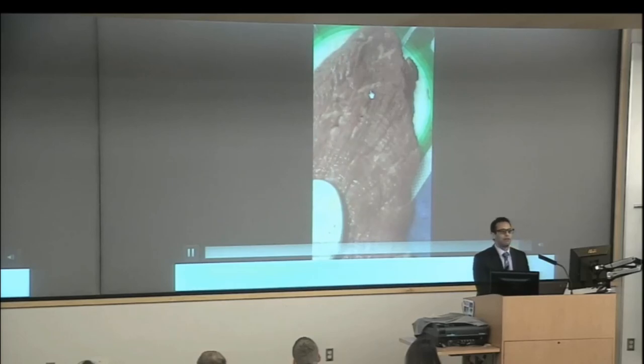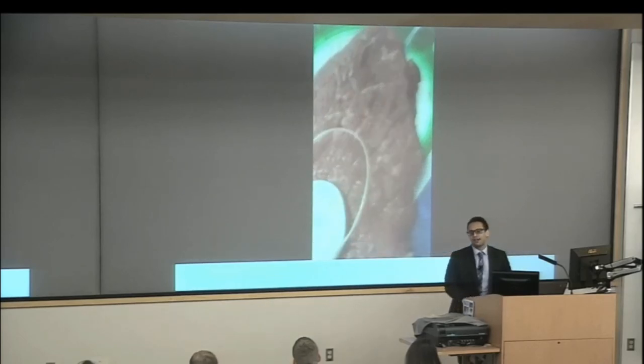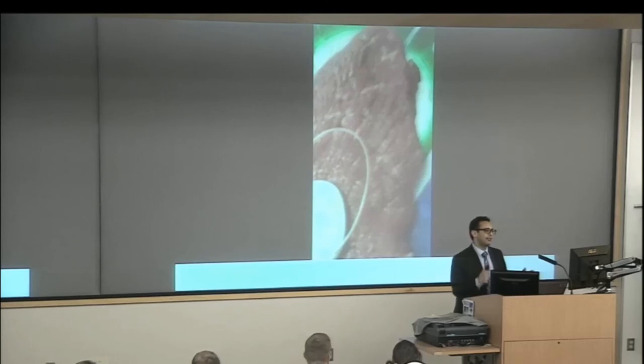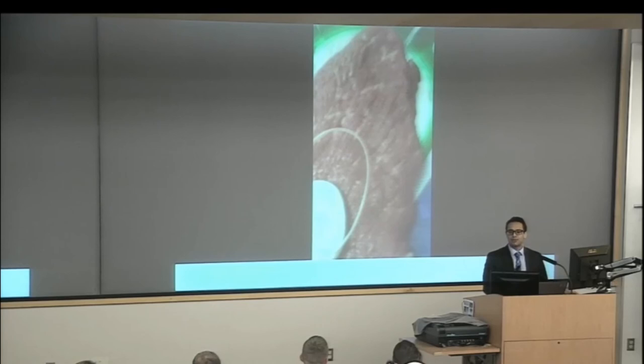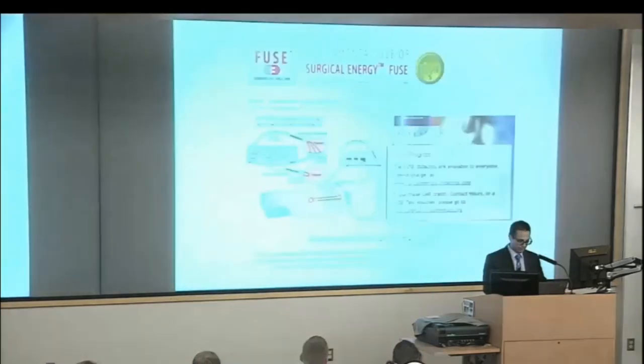You can minimize this in the OR if your patient has a pacemaker or implantable device. You can use ultrasonic devices, which don't cause any interference. You can use low voltage settings and low power. Don't put it all the way to 50 coag every time. Try to minimize that, and try to keep the path of the current away from the pacemaker. There are a variety of tricks to get around it, and really owning these instruments can make you safer in the operating room.